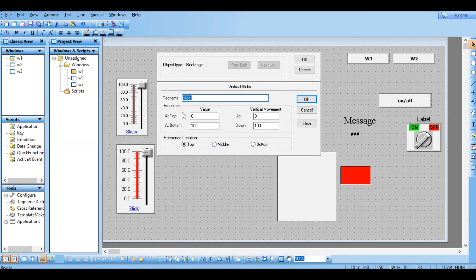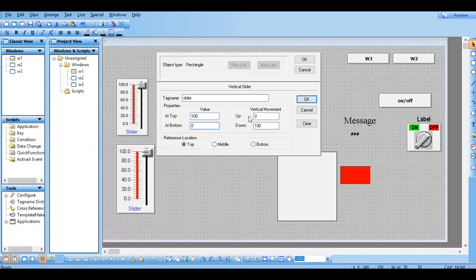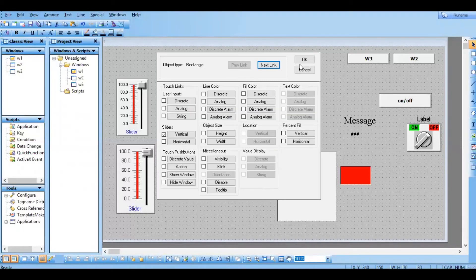Vertical — it was mentioned as top but that did not happen. Initially it was bottom setup, and the values were set accordingly. Whenever you go for the top location, you need to change so that top is 100 and bottom is 0. Whenever you are changing the reference location, you need to change this value too — make it 0.